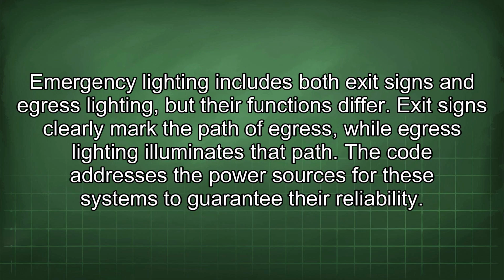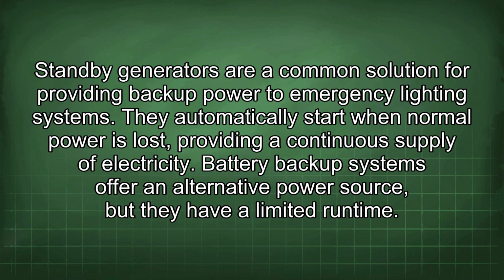Emergency lighting includes both exit signs and egress lighting, but their functions differ. Exit signs clearly mark the path of egress, while egress lighting illuminates that path. The code addresses the power sources for these systems to guarantee their reliability. Standby generators are a common solution for providing backup power to emergency lighting systems. They automatically start when normal power is lost, providing a continuous supply of electricity.